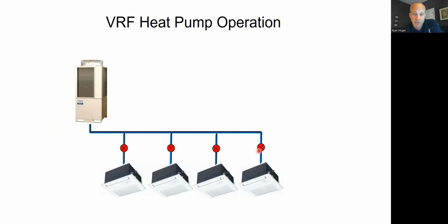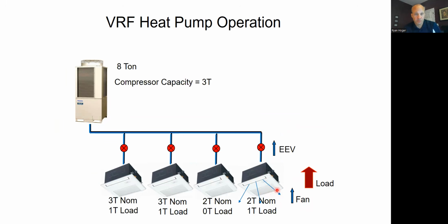It's showing them on the piping here, but they're actually in the box. As those zones need less capacity, they throttle their expansion device, and they can change their indoor fan speeds. Either they'll have a fully variable one, or they'll have like a 3-speed fan or something like that. So in this particular example, we have an 8-ton model outside, and my peak loads for these guys are 3 tons, 3 tons, 2 tons, 2 tons. So you notice right off the bat, I have 10 tons of capacity connected to an 8-ton unit.